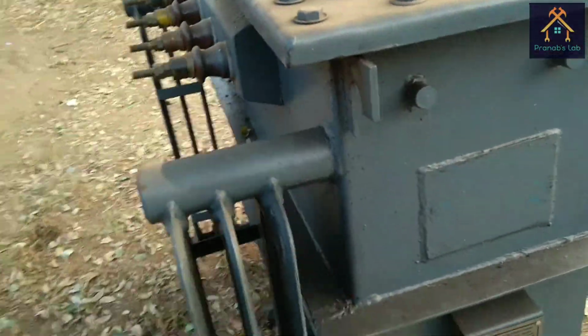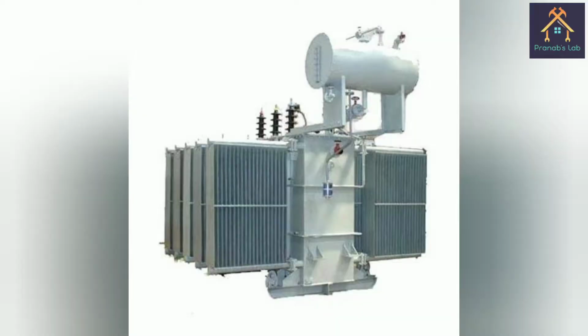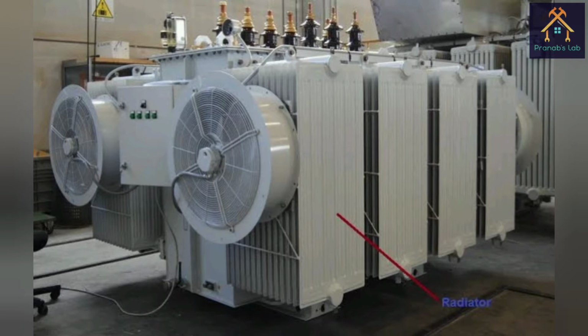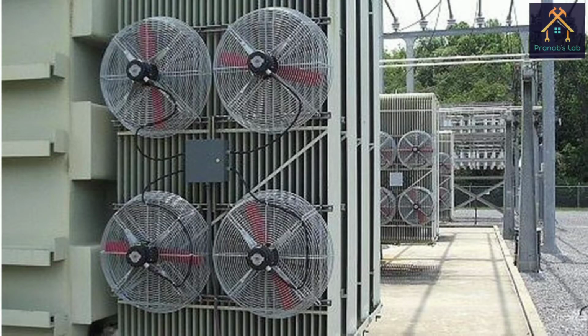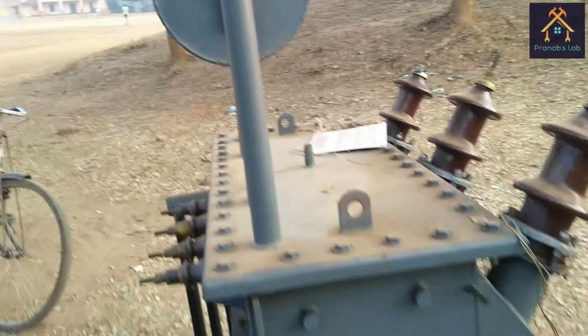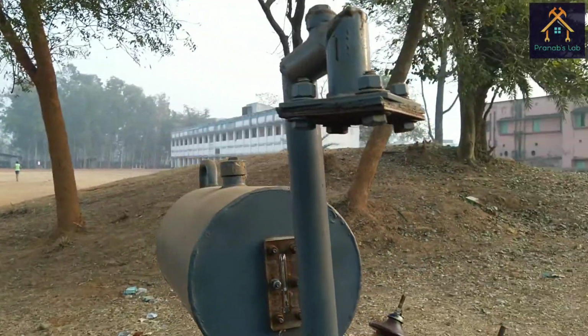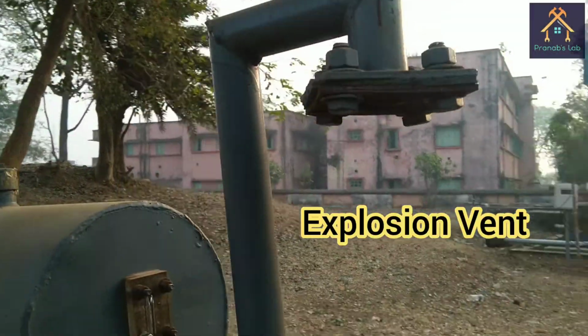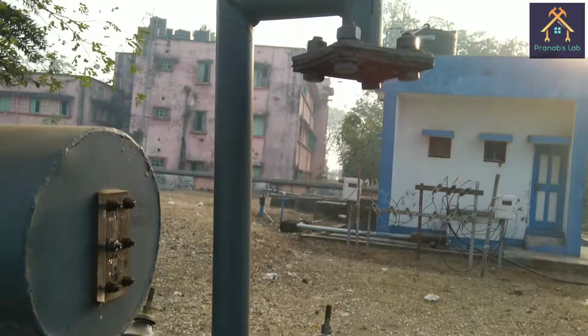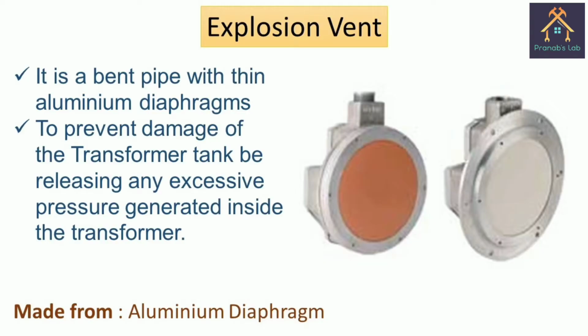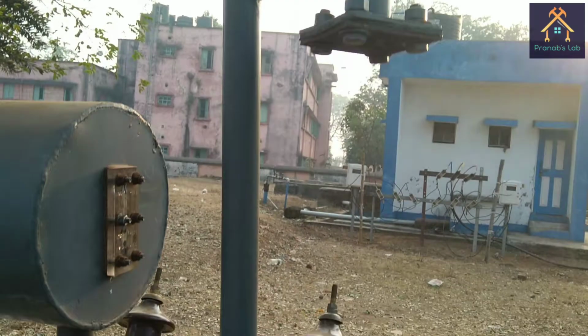For a larger size of transformer, the heat production is more, so the number of fins will be more, and a separate fan is used for cooling by forced air. Now you can see this is the explosion vent of the transformer. Basically, it is a bent pipe with a thin aluminum diaphragm. It is used to prevent damage to the transformer tank by releasing any excessive pressure generated inside the transformer by heating.